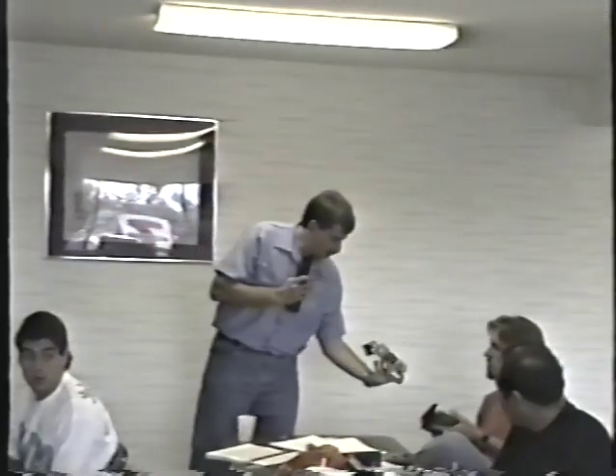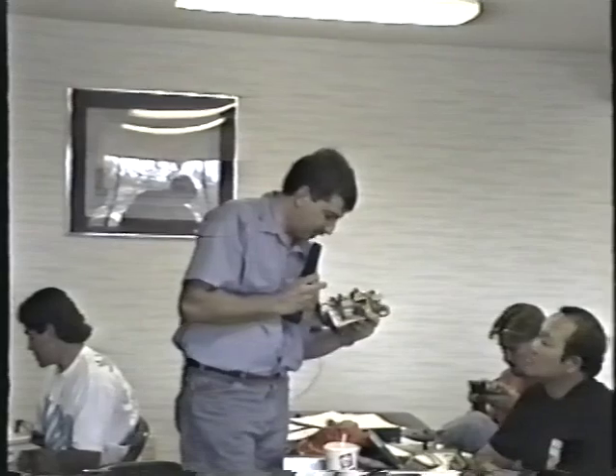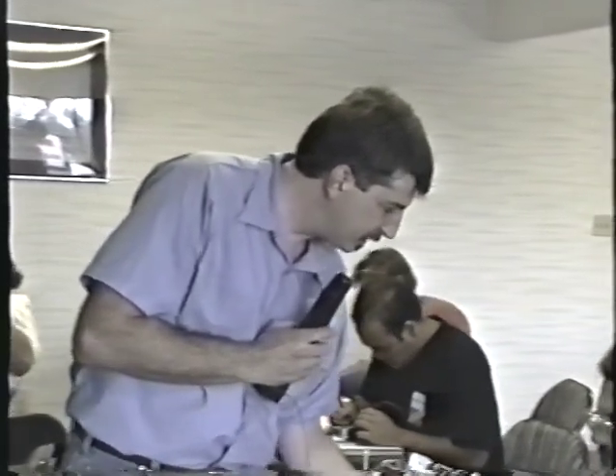See this one right here? See this guy, Wayne, how it's slightly bulged up? Yeah. And in fact, we're probably going to want to change all these, to be honest with you. See, this one is slightly bulged. Not by a lot, but it's enough to tell you that it's bad.